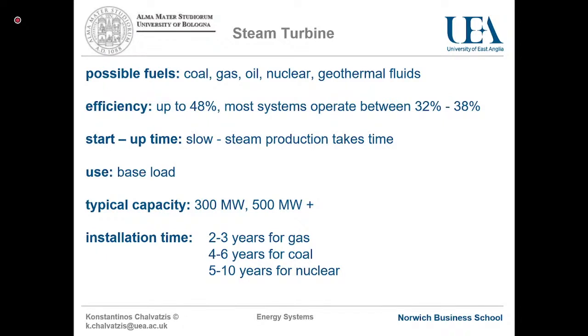Startup times: relatively slow startup. Steam production takes time and cannot be adjusted very rapidly, so if energy demand changes, you're probably going to need something else to respond to that change — not your steam turbine. Typical use is what we call base load, or scheduled load as I'd like to say — loads you know will be there and can plan in advance. If you know there will be demand for energy at a certain time, you can start preparing a couple of hours ahead from a cold run and have the system ready when you need it.